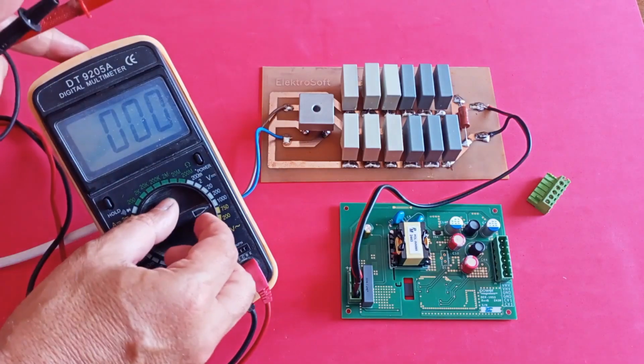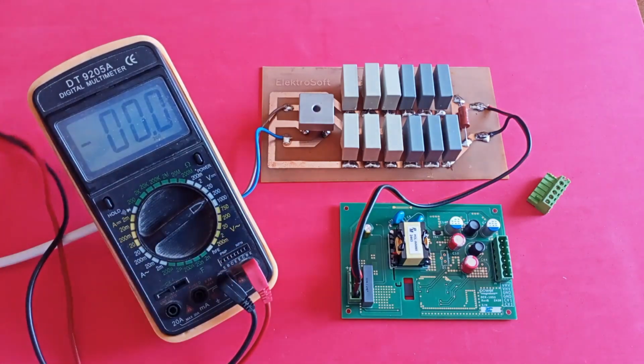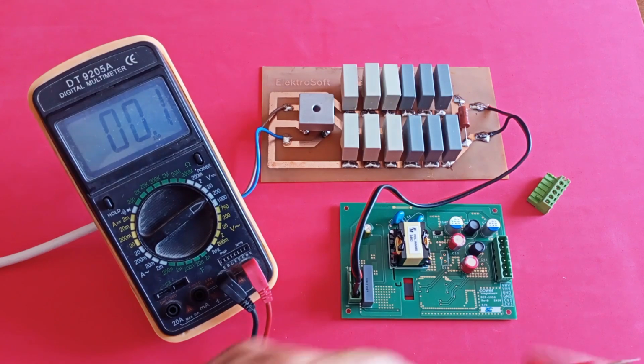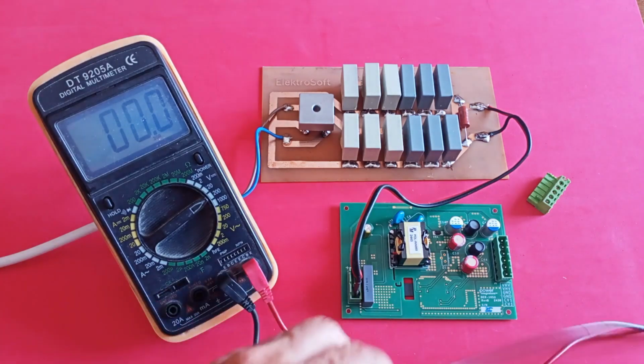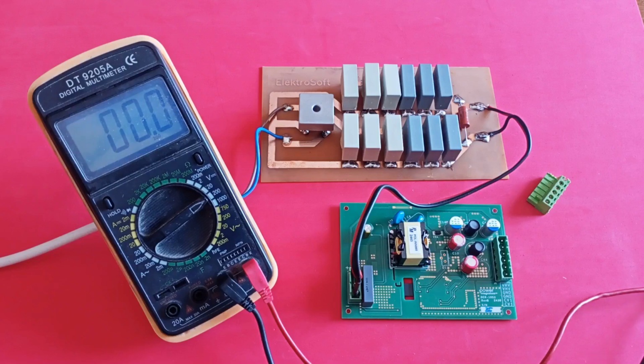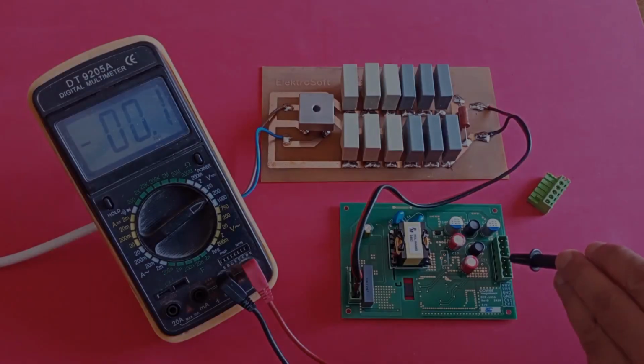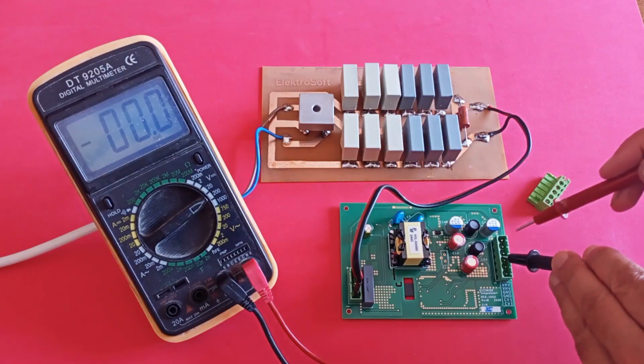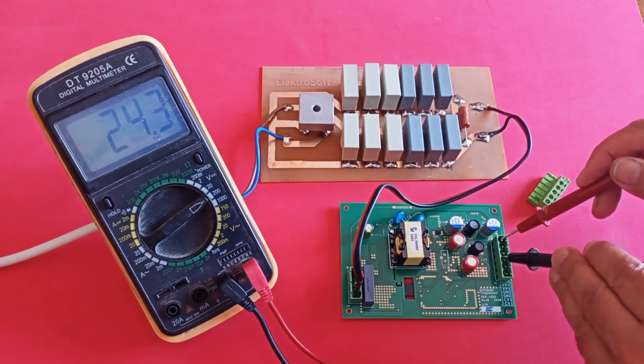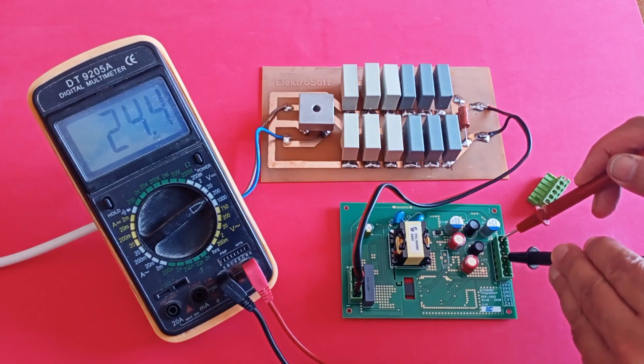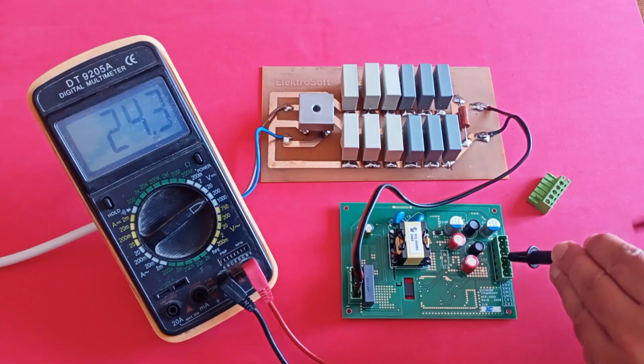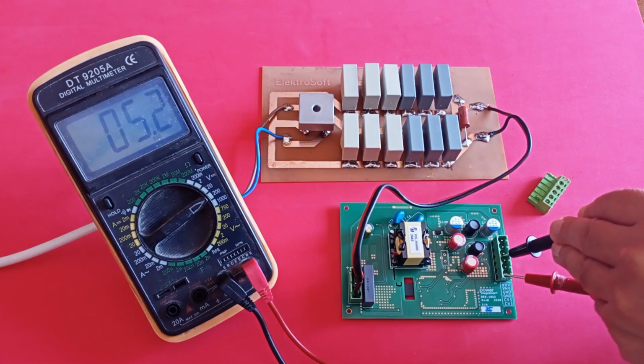Lowering the DC range to 200 volts, we measure the VHV and CV1 outputs. Placing the ground probe on GND, the tester reads almost 25 volts on the VHV output. Then we measure the CV1 output, where we read a voltage of about 5 volts. Note that no load was intentionally connected to the output.